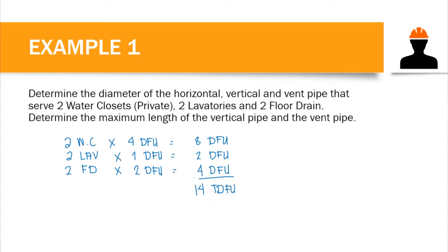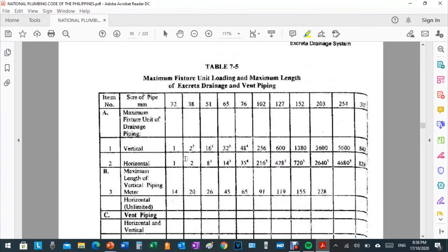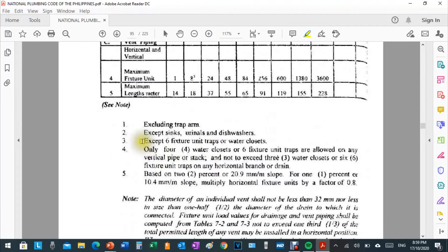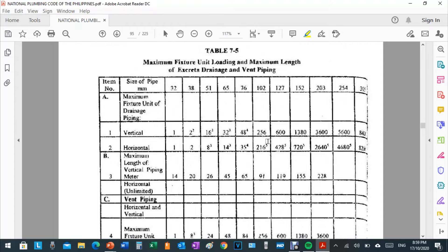We proceed to Table 7-5 with a total drainage fixture unit of 14. First, let's determine the size of our vertical pipe. With 14 DFU, we fall between 2 and 16, so we choose 16. However, 16 has superscript 3. Note number 3 says: except six fixture unit traps or water closets. Since we have water closets connected to that pipe, we do not choose 16. We move to the next higher value, which is 32 — but 32 also has superscript 3, so we move again.